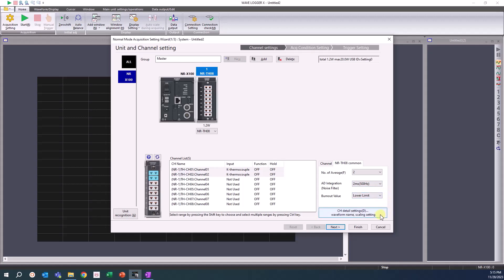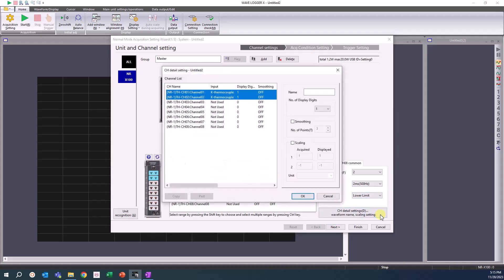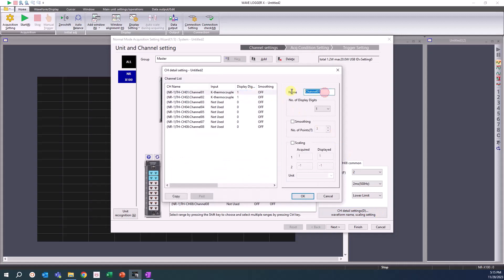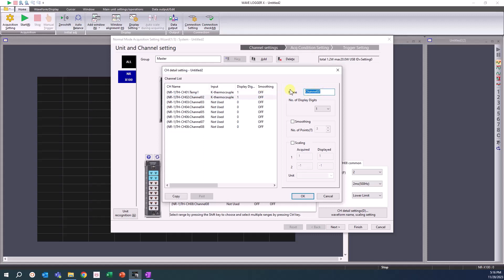Additional channel detail settings can be found here. In this window, you will find the location to name channels. For this example, channel 1 will be named temp1. Channel 2 will be named temp2. This is also where you can change the number of displayed decimal digits, smooth the displayed waveform, and scale inputs with 2-point scaling.